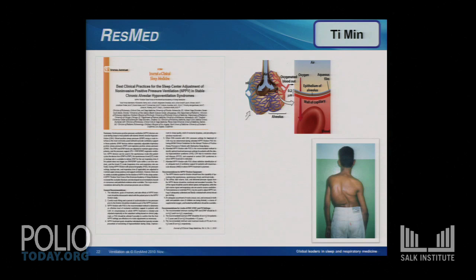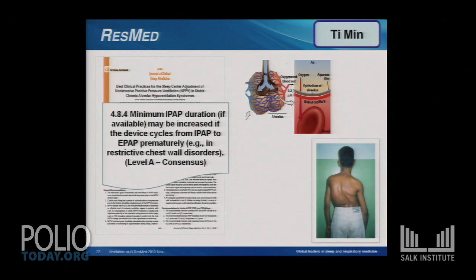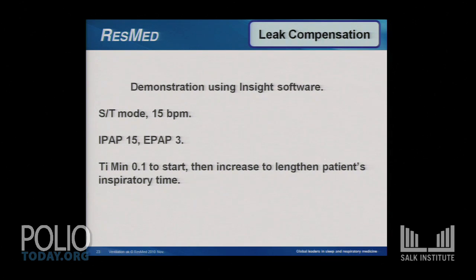So this particular group of physicians in this consensus statement said a minimum IPAP duration, if available, may be increased so that the device does not cycle prematurely. Now what they're talking about here is TI minimum, being able to have a device that allows you to set a minimum inspiratory time. So again, we're talking about those brackets, the TI minimum and the TI maximum, and setting this TI minimum ensures we have adequate time for gas exchange.